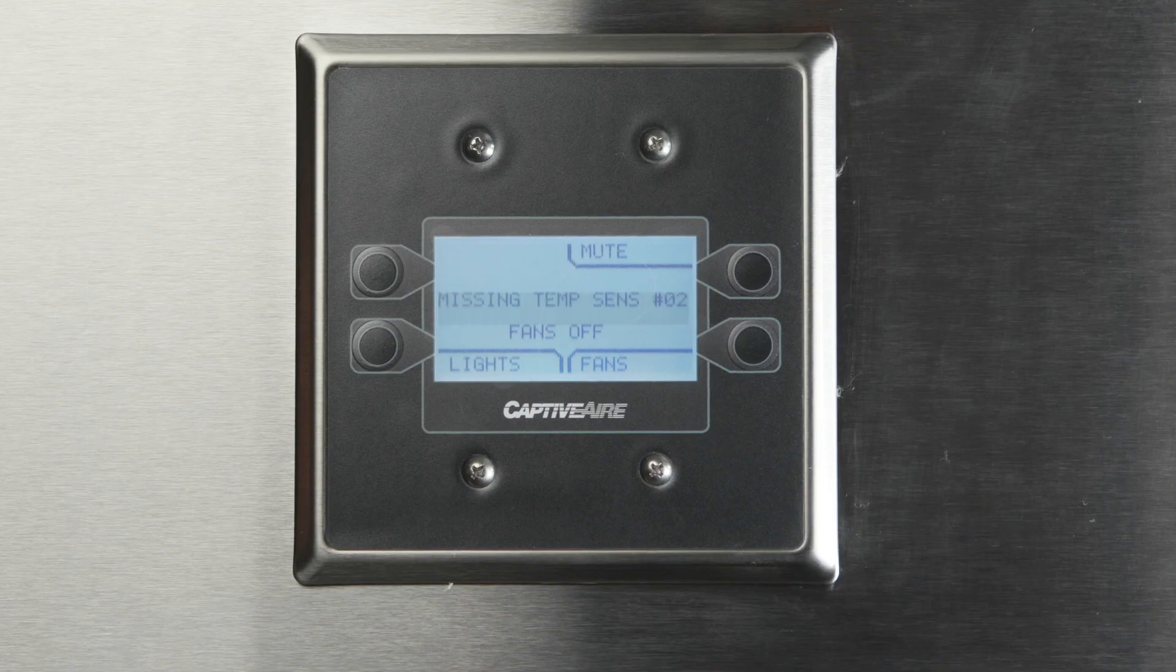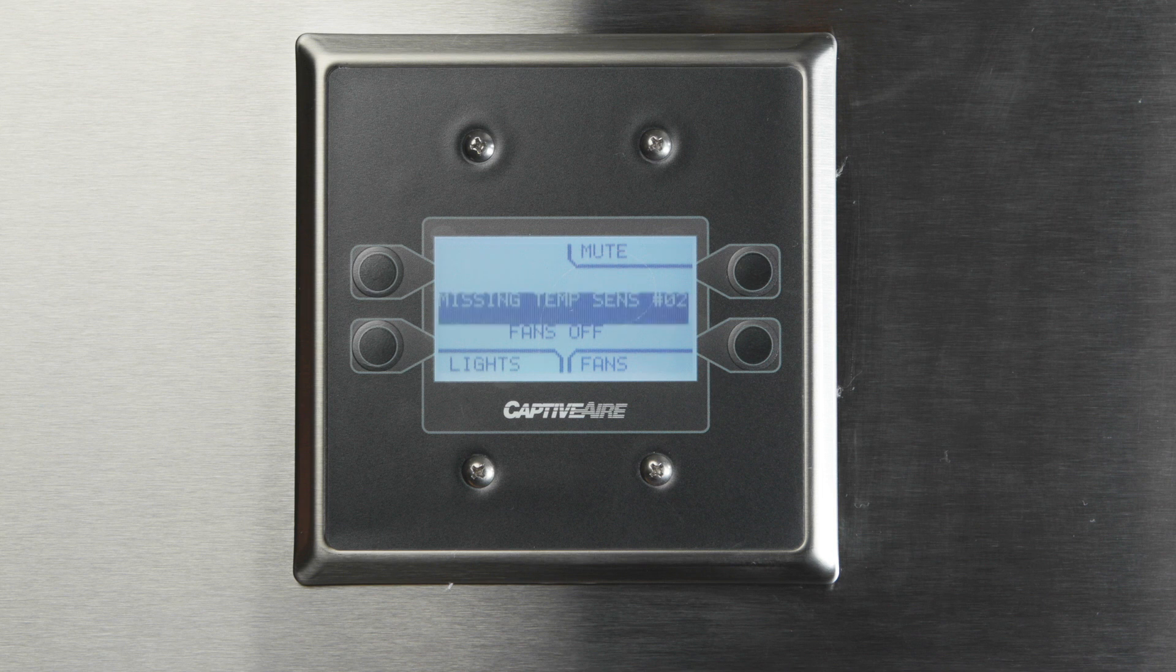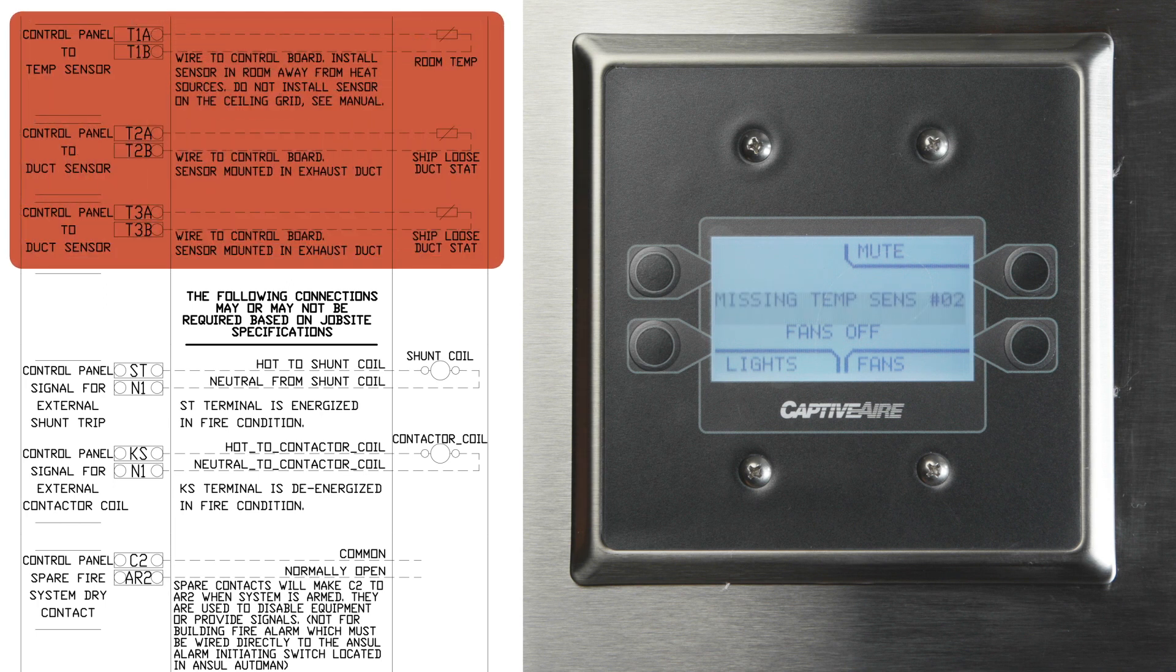The last most common issue is the HMI showing missing temp sensors. This simply means that the circuit board has been programmed for a specific number of temp sensors and is not detecting all of them. Verify all your sensors got wired to the T terminals. Again, the wiring diagram will show you the number of sensors required for your specific job.